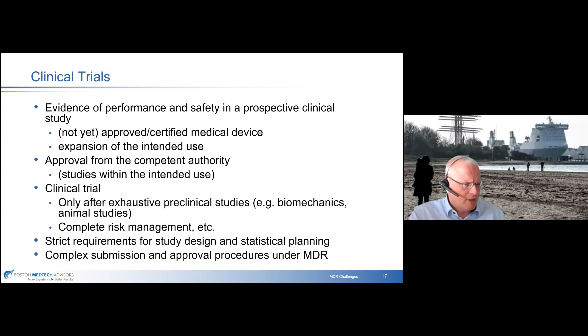Such studies require the approval from at least one competent authority in Europe. And this is not required: studies within the intended use are exempt from that approval, of course, as we see it also in America. And the plan for a clinical trial can only be submitted after you have exhaustive preclinical studies and a complete risk management, quality management, etc. So you need to do everything to minimize the risk of the exposed patients in the study. There are strict requirements for study design and statistical planning, and I think that we have a pretty complex submission and approval procedure under the MDR. I would even say it's more complicated than before, but we have to see over time how that really works out.